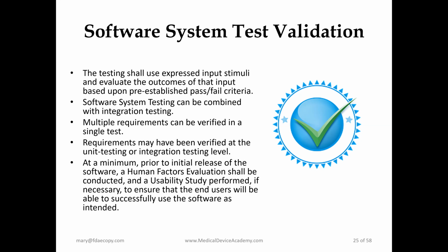Another consideration is your human factors evaluation and potential usability study. This is an important one that the FDA has been requiring a lot: getting your device in the hands of actual end users and making sure that they are able to use your device as intended. So unless your device is extremely similar to another one that's already on the market, or this is just an update to an existing system that has already been validated in the hands of users, then you're typically going to be looking at a required usability study of some level.